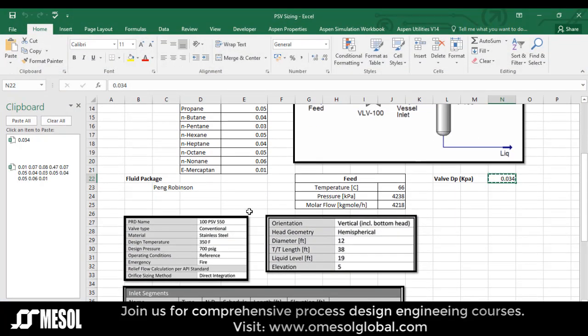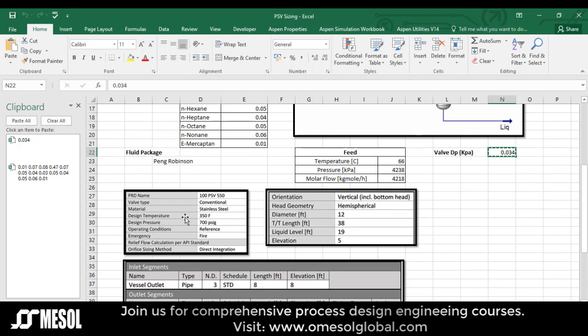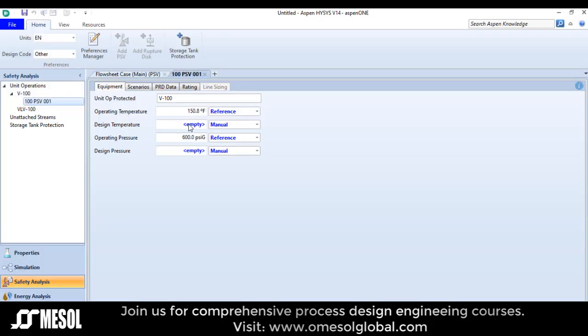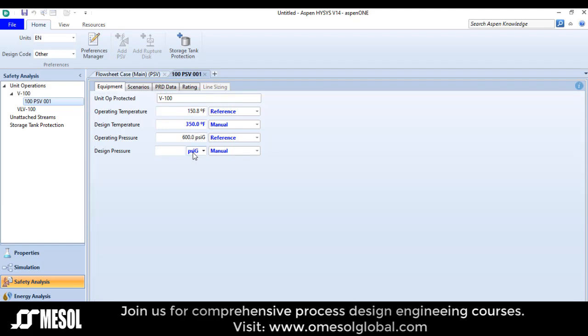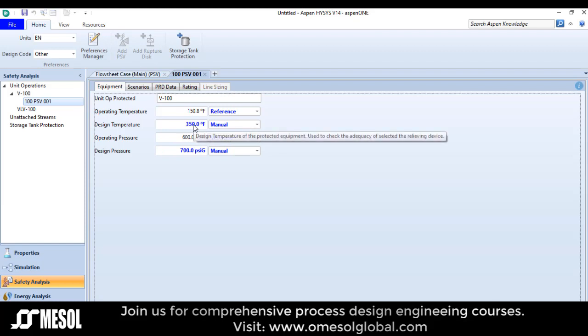Now double click the PSV and provide the design temperature and pressure. In my case the design temperature is 350 and the pressure is 700 PSI. Usually this design temperature is the vessel design temperature.